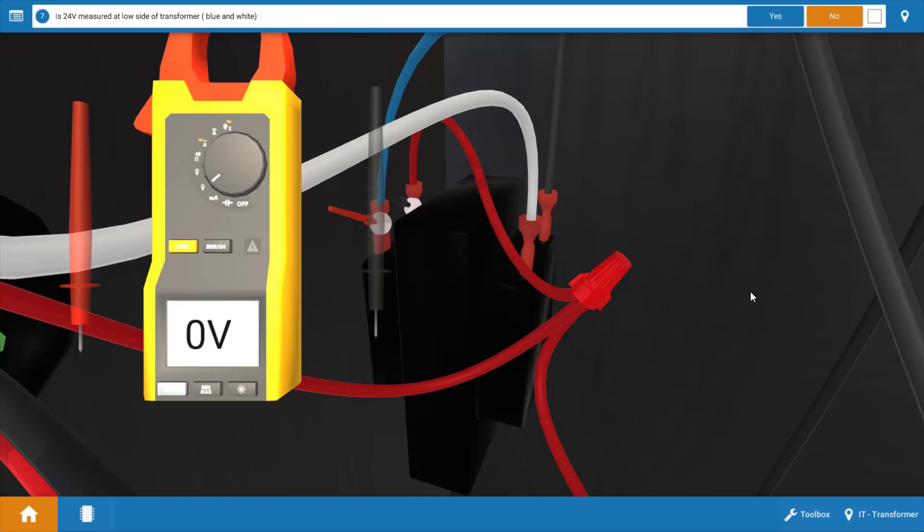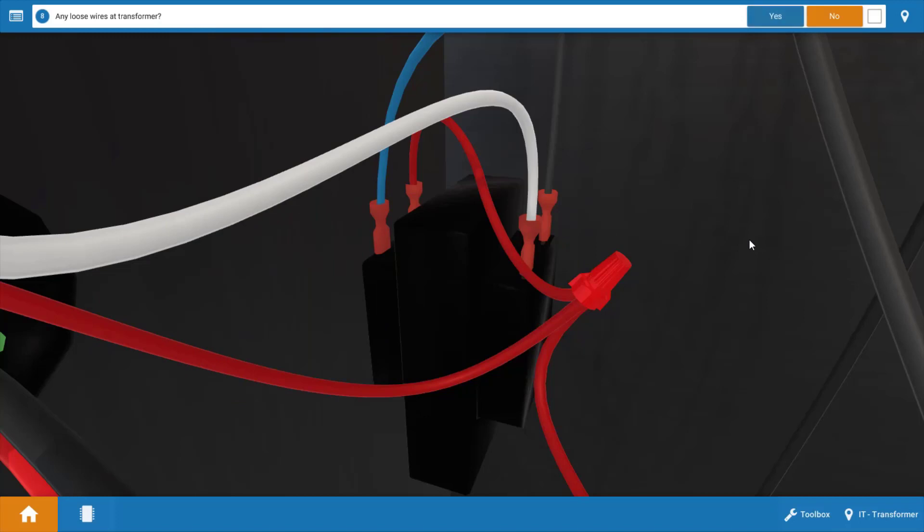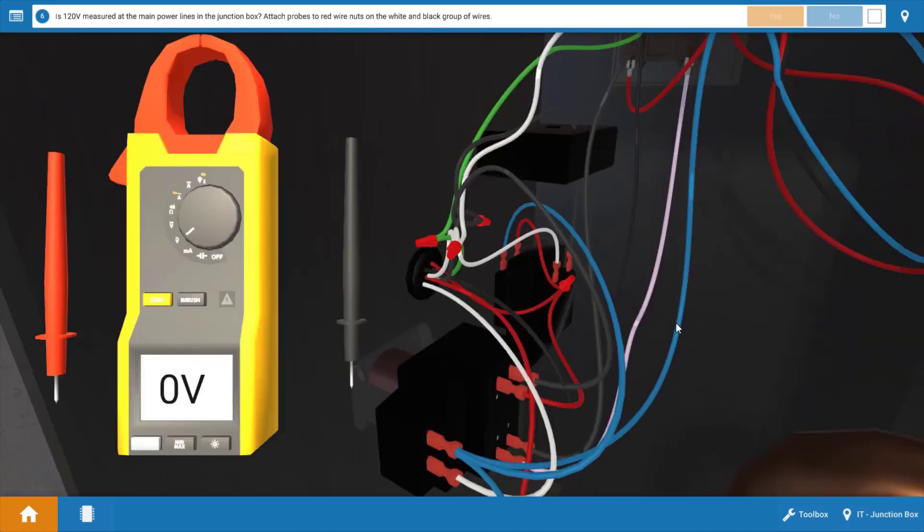Well this means one of two things, either the transformer is faulty or possibly we don't have power to the transformer due to a loose connection or a broken wire. So we're going to click no on the procedure guide because we measured zero volts.